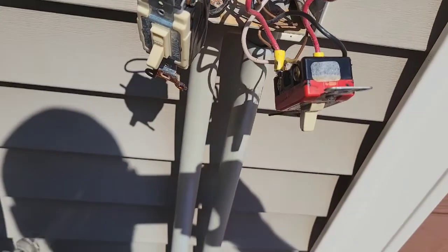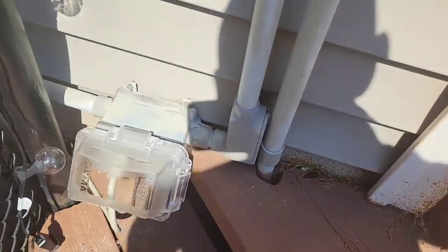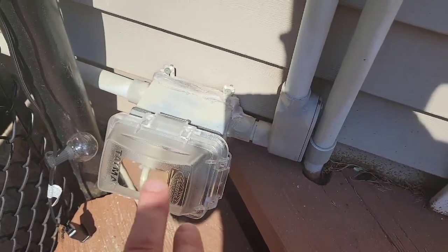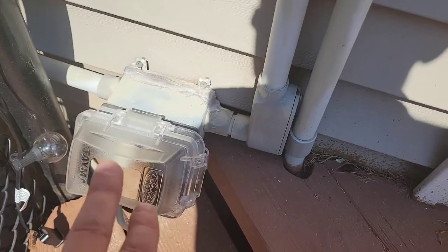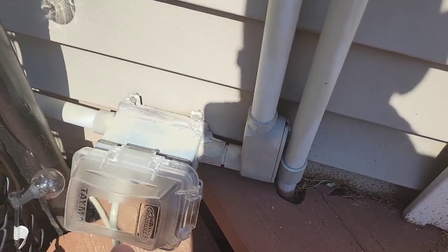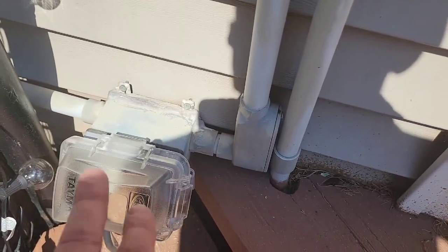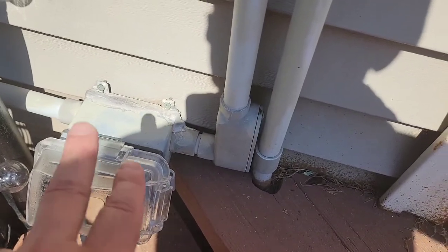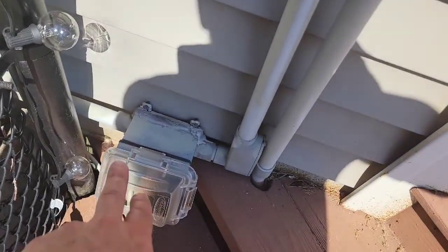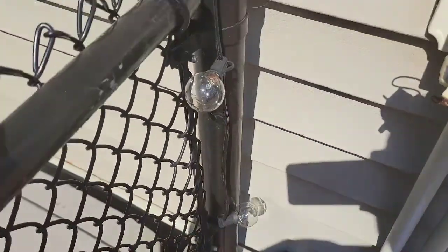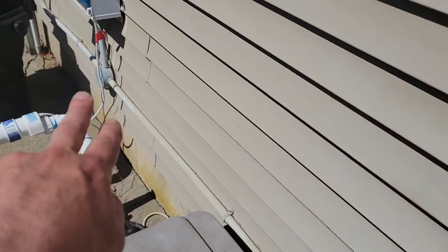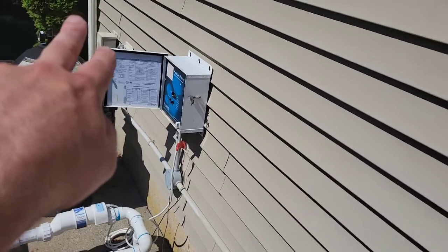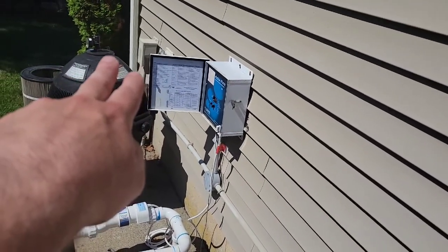Well, long story short, what I determined was this receptacle that's always on is fed independently through the house and the garage in parallel with another receptacle. That's why it was always on, and that power was used to come through this switch, then back down. So the hot lead went through the switch back down. The ground lead in that receptacle already went through that junction box over there and fed independently the lighting transformer at the end of the string.